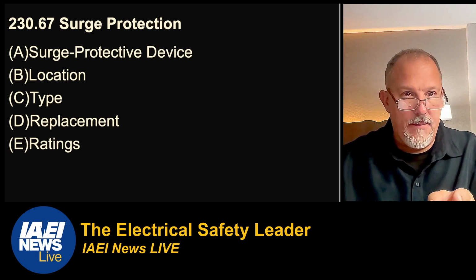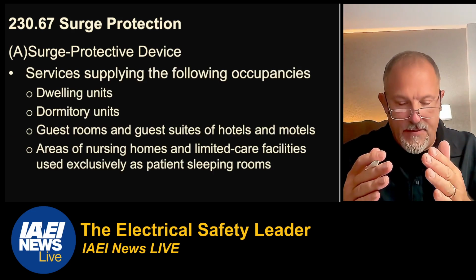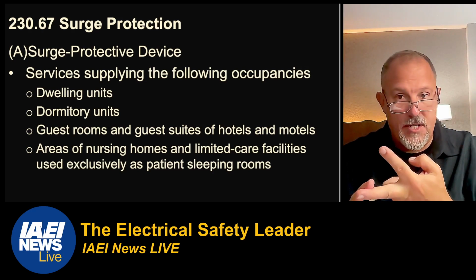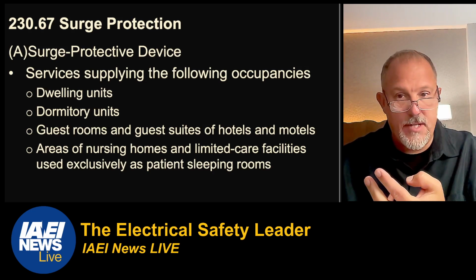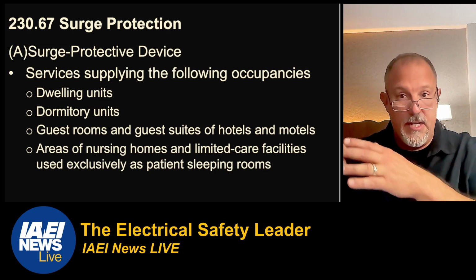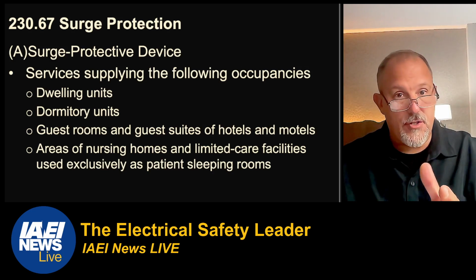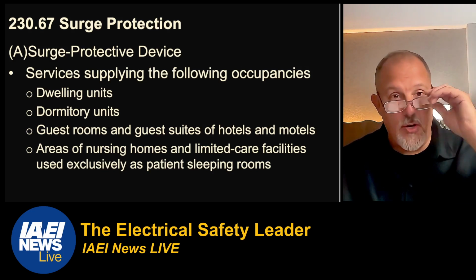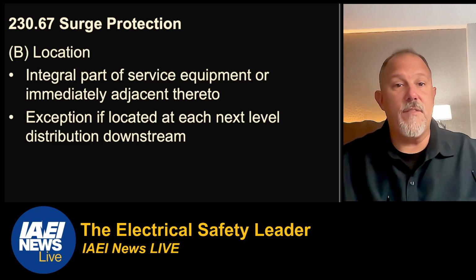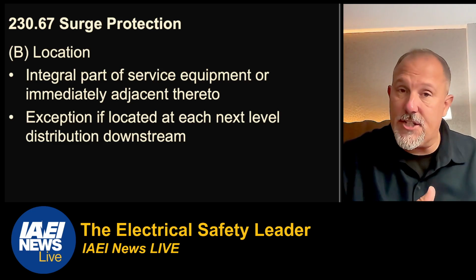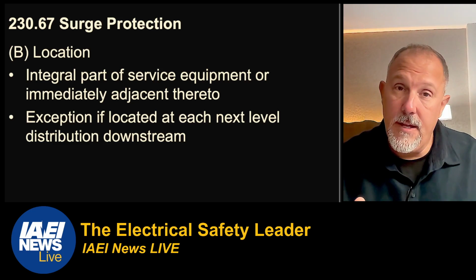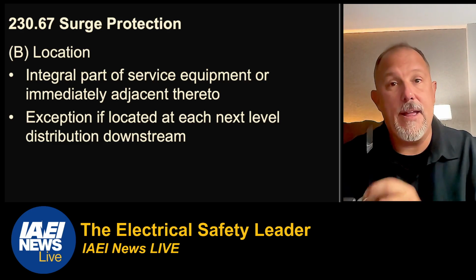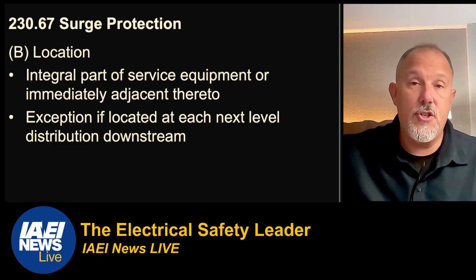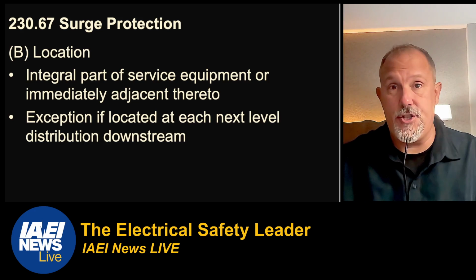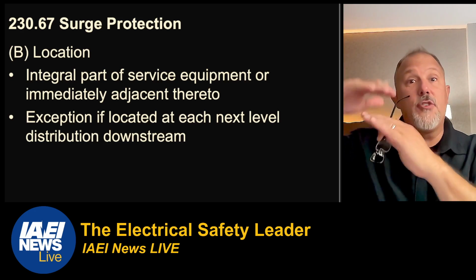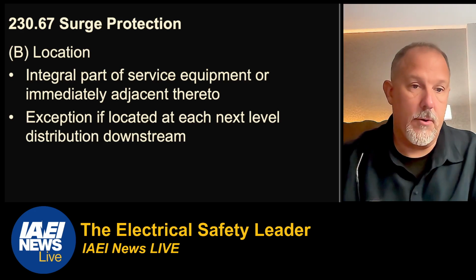So what they did in A was say, look, you need to have it for dwelling units, but also dormitory units, guest rooms and guest suites of hotels and motels, and areas of nursing homes and limited care facilities used exclusively as patient sleeping rooms. So those locations now have surge. Remember, before it was just dwelling units. They expanded beyond dwelling units. In B, you have the location. It has to be an integral part of the service equipment or immediately adjacent thereto. And the most important thing is the lead length between that bus and that surge protected device. Don't be extending it. The shorter you can get it, the better off you are, because every inch reduces the level of protection. It increases the let-through voltage. Very important.